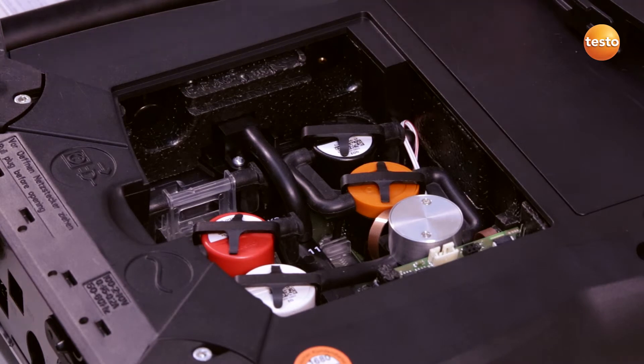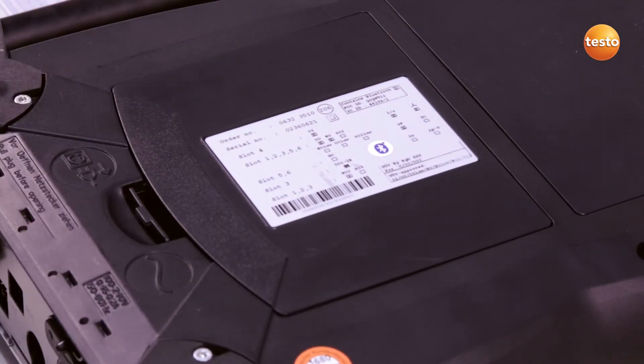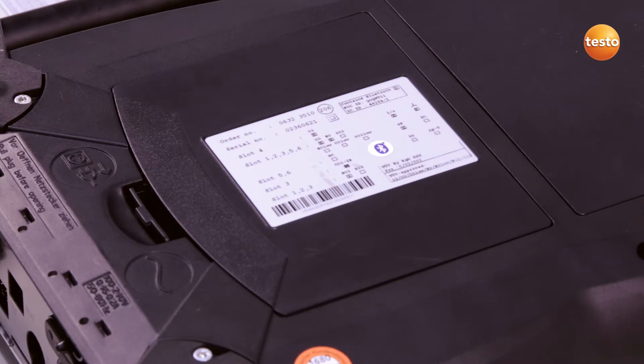Finally, I replace and close the sensor compartment cover. After replacing the sensor, a new measurement can be carried out immediately without adjusting the sensors with test gas, as the sensors are calibrated ex-works.